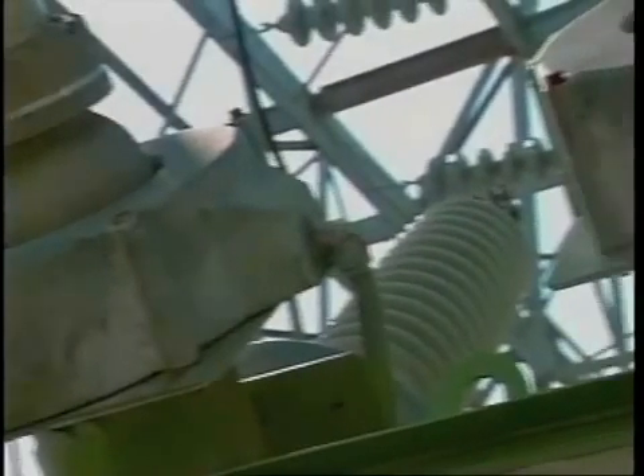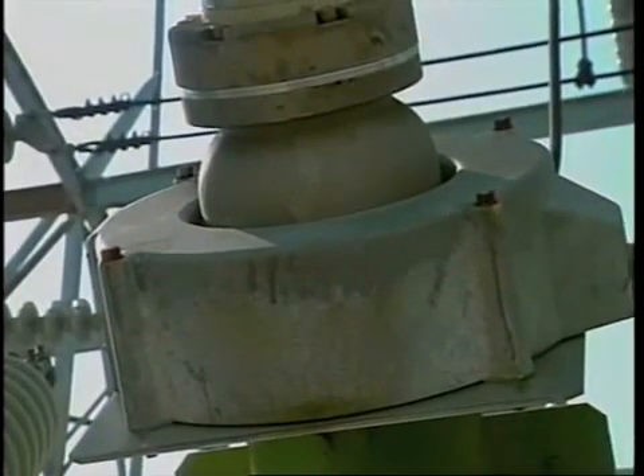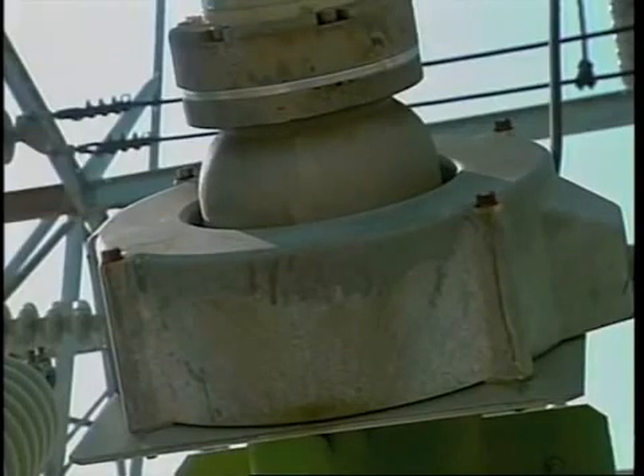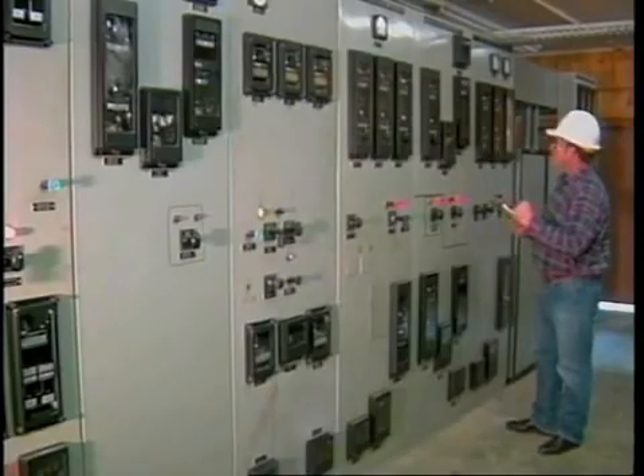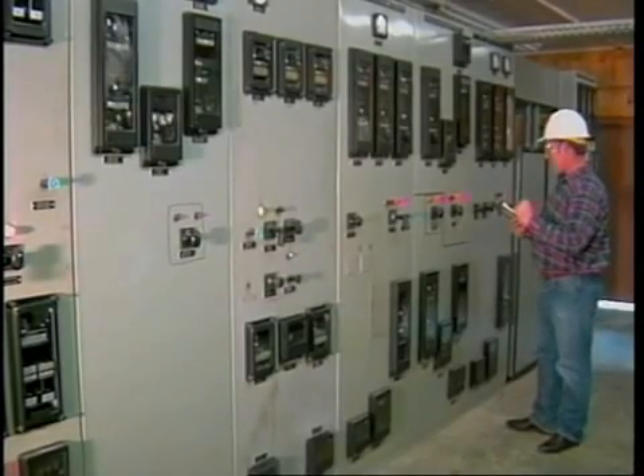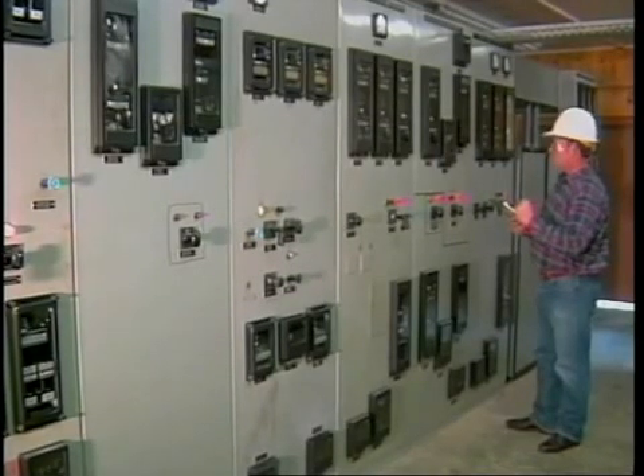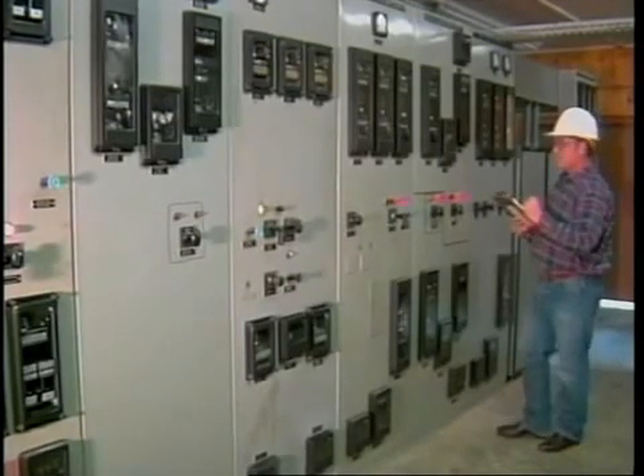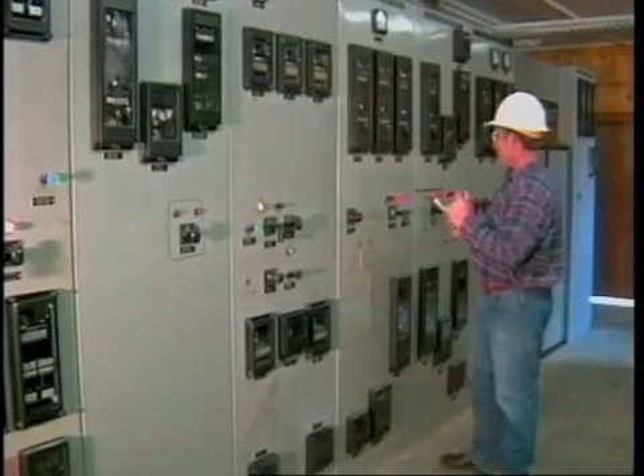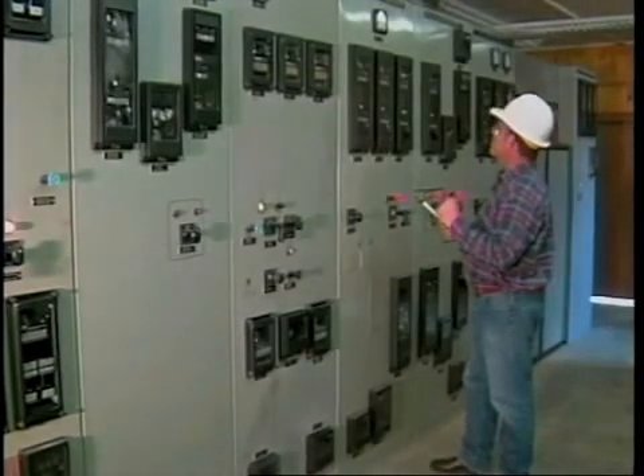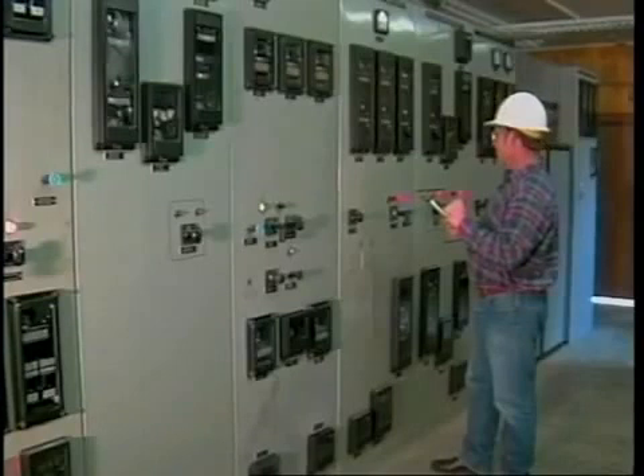Current transformers are a vital part of the electrical protective system in the plant. Current transformers reduce the current in the power circuit to a level that can be handled by protective relays and meters, thereby isolating them from the power circuit. In this program, we'll discuss generally accepted safe guidelines for work with this type of equipment.